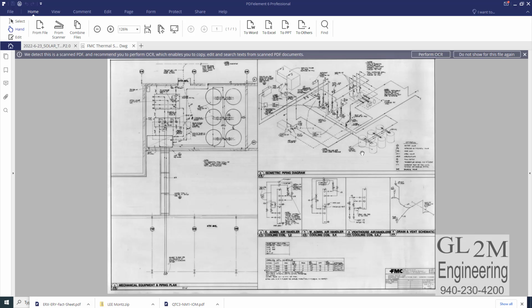It's not meant for loads that are steady, but it's an interesting concept in that it allows the utility company to not have to build new infrastructure to support the peak load, because that's their problem. They have to build generation plants and wires to support the worst case hottest day of the year in their area. And if you can shift load to off-peak hours, then they don't have to build infrastructure.